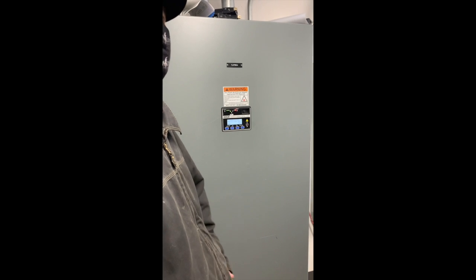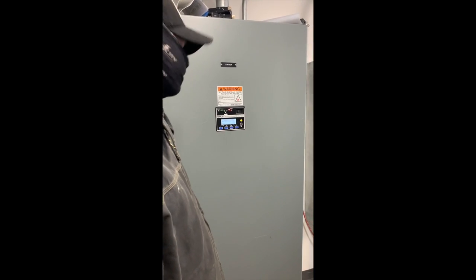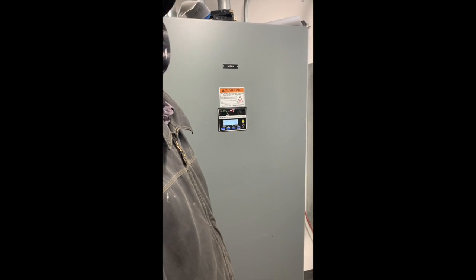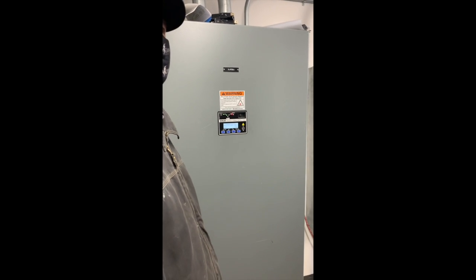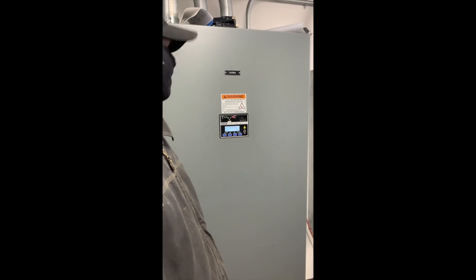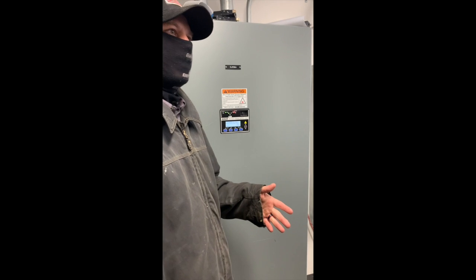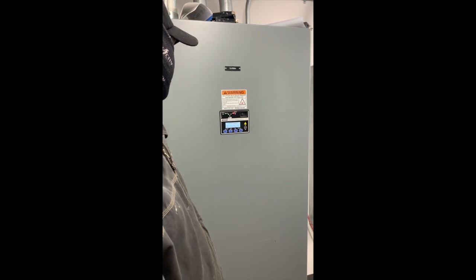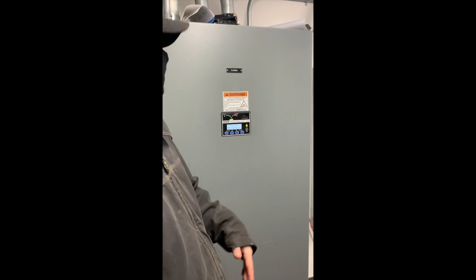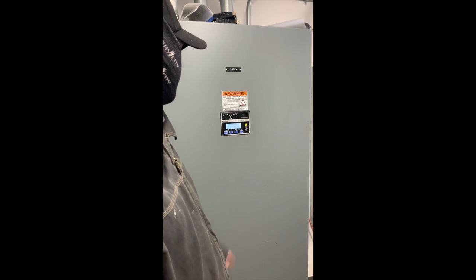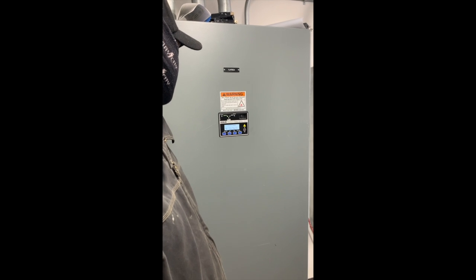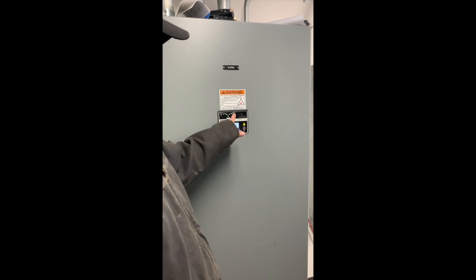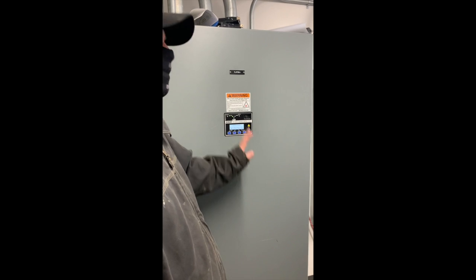You've got to keep it under a certain number of hours if you don't have to run it during an emergency situation. For testing, they want us to do it minimally. Say you meet your time requirement, and then you just hit end test, and the generator will shut down, and you can see the voltages dropping. Boom, off emergency source, and you're back to system ready.